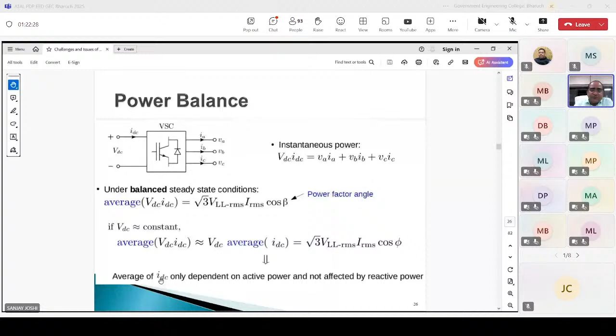STATCOM and BESS, battery energy storage system. If this switch is open, this is only STATCOM. This is your capacitor on the DC side of your VSC with some voltage. Remember that because there is only a capacitor, the STATCOM cannot supply any active power. So on the AC side of VSC, it cannot supply any AC power. That's why PAC is equal to 0. QAC can be controlled, likewise as I have discussed in my previous slide. Now, a capacitor on the DC side is adequate as average IDC is 0 - average IDC is 0 because, as I concluded, average of IDC depends only on active power, whereas here no active power is supplied by the STATCOM. So a smaller size of capacitor is also enough at the DC side terminals of this VSC.